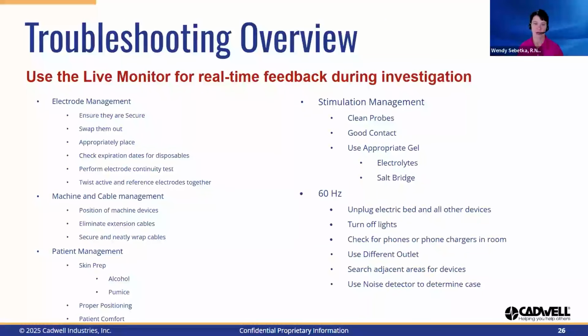Before we continue, I'd like to take a quick moment to review the troubleshooting techniques we discussed. Electrode management includes swapping out electrodes and ensuring they are secured and appropriately placed, twisting active and reference electrodes together, and checking expiration dates for disposable electrodes and gel. Performing an electrode continuity test is a good test for reusable electrodes. Machine and cable management should include proper positioning of the machine and amplifier, securely connecting cables using the appropriate connectors, neatly wrapping excess cables, and making sure the power cord is directed away from the device. When possible, eliminating extension cables, even if they are hospital grade, is ideal.